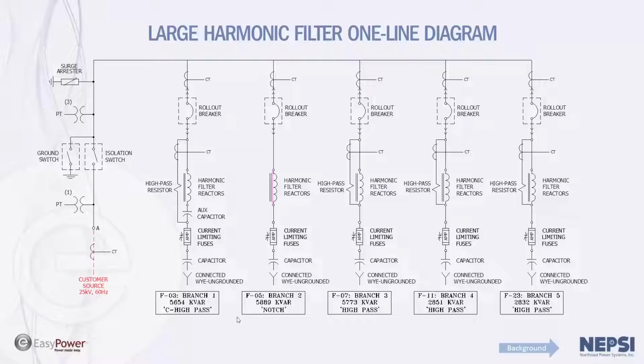It consists of C-high pass, notch, and standard high-pass filters. You can see that we have rollout breakers for switching the various branches of the filter system. This filter system also included an automatic control system for regulating power factor and controlling voltage distortion within the mine's process plant.